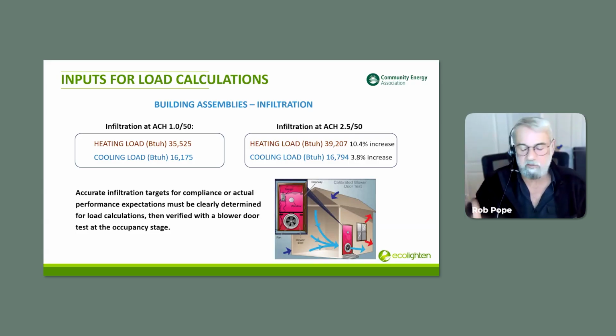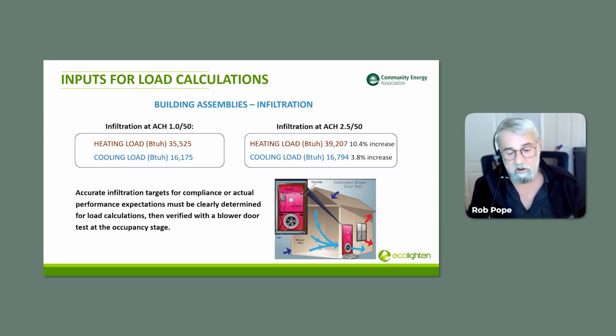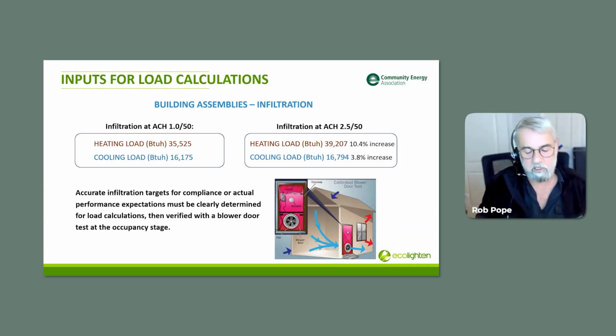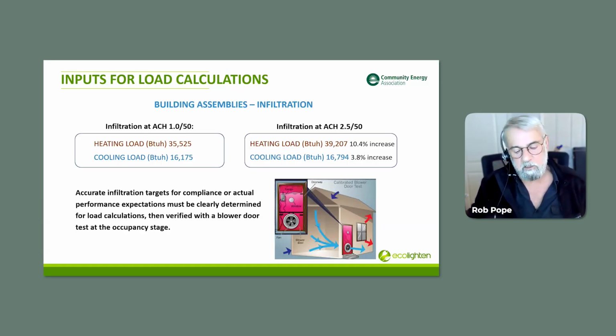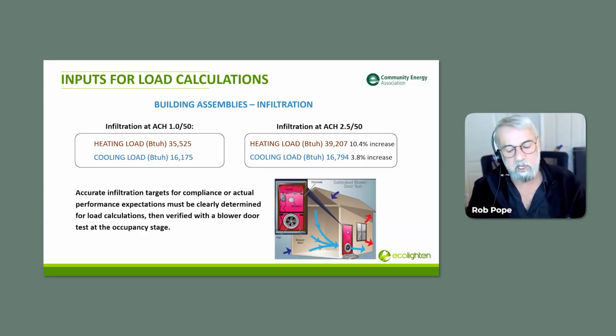As a designer, I say 5.5. Okay, let's throw a couple numbers on there, make it 7.5, to build a little resilience in, and then verify it. Because if there was a target set, somebody's going to come back with that same blower door kit and see how we did. Usually by then it's too late, you've already installed the system.